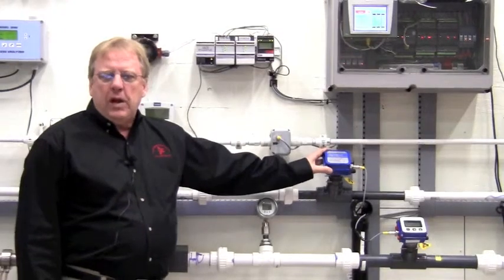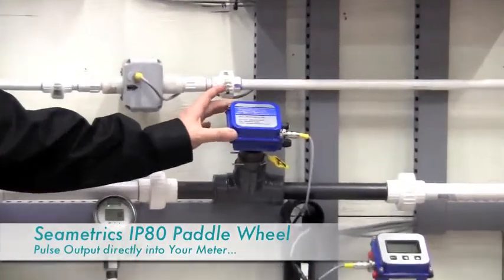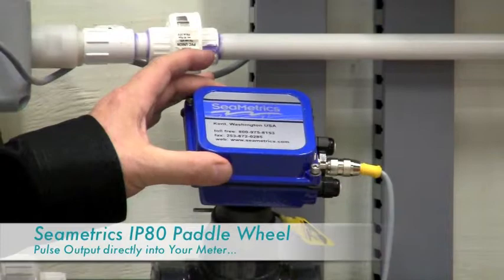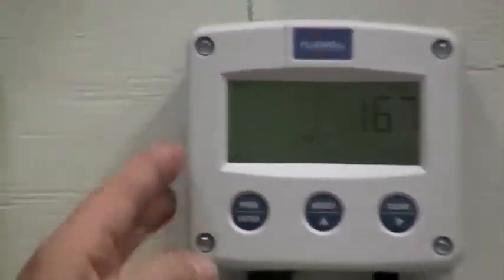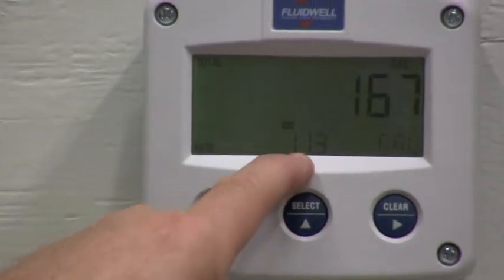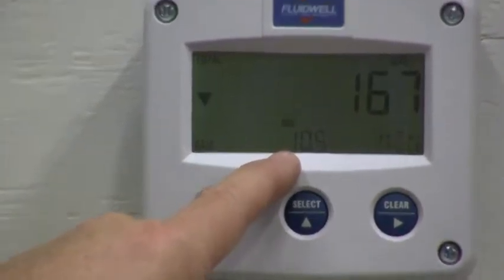Next, we also have installed in one of our one-inch lines a Seametrics insertion paddle wheel flow meter. This meter has a blind unit with no display, and we're taking the pulse output from this meter up to our Fluidwell display mounted on the wall here. You can see our gallon per minute reading, which is 11.3, and then the top display will be your totalizer that will count in gallons for you.